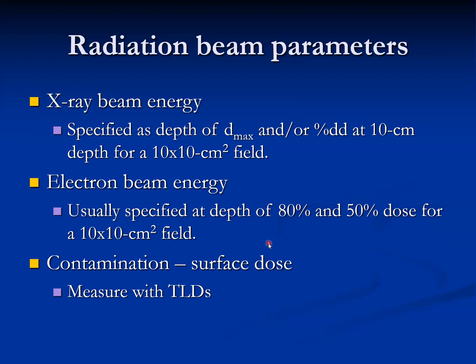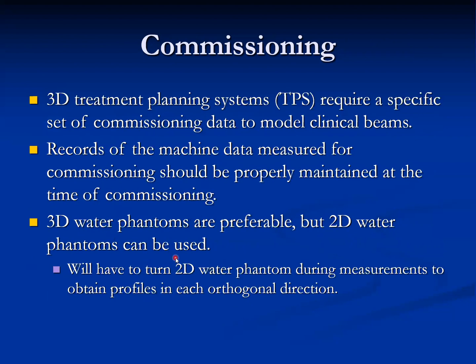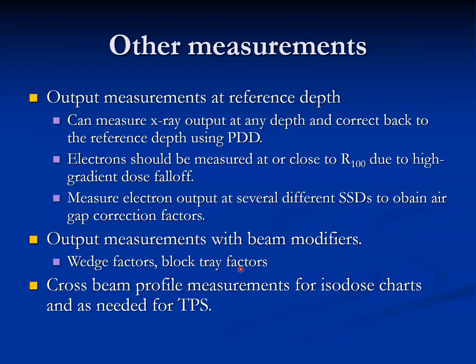Surface dose contamination measurement will be measured with film or TLD. Commissioning is the gathering and processing of measured data needed to deliver a prescribed dose with a clinical setup. It establishes a table of relative measurements so that monitor units can be calculated. Each machine energy and modality is commissioned separately. Special procedures usually require additional commissioning, such as IMRT, VMAT, stereotactic therapy. 3D treatment planning systems require a specific set of commissioning data to model the clinical unit. 3D water phantoms are preferable, but 2D water phantoms can be used. Depth dose recommendations are typically provided by the vendor.